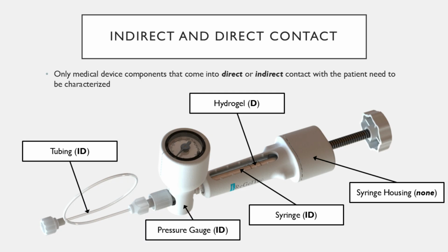Whereas any of the other plastic parts, the metal parts that make up this delivery device that never touch the hydrogel are going to have no toxicological consequence to the patient and therefore have no effect on the chemical characterization profile of the medical device.